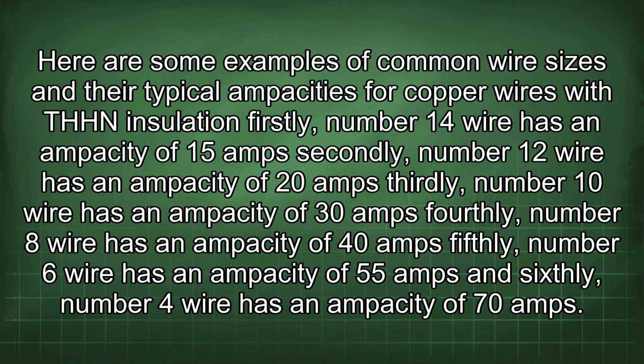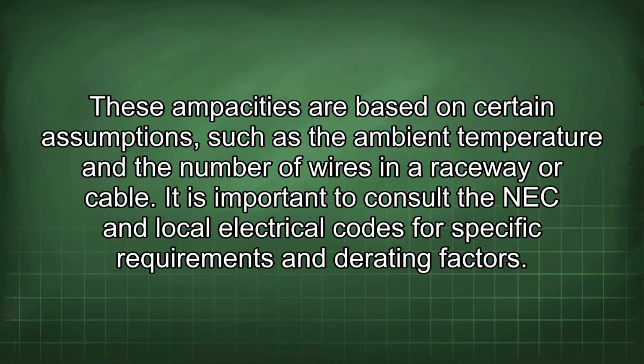Thirdly, number 10 wire has an ampacity of 30 amps. Fourthly, number 8 wire has an ampacity of 40 amps. Fifthly, number 6 wire has an ampacity of 55 amps. And sixthly, number 4 wire has an ampacity of 70 amps. These ampacities are based on certain assumptions, such as the ambient temperature and the number of wires in a raceway or cable. It is important to consult the NEC and local electrical codes for specific requirements and derating factors.